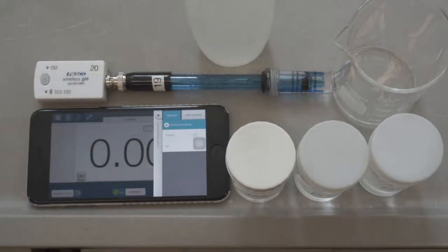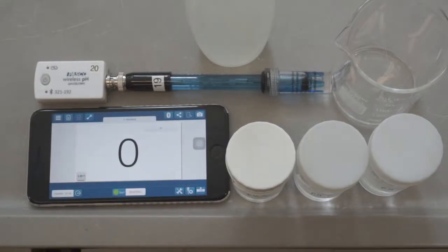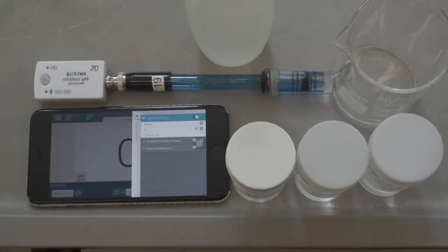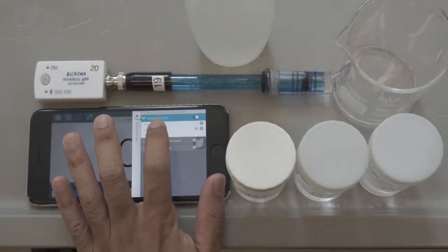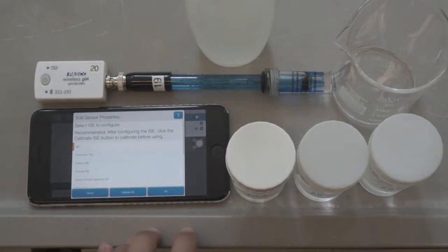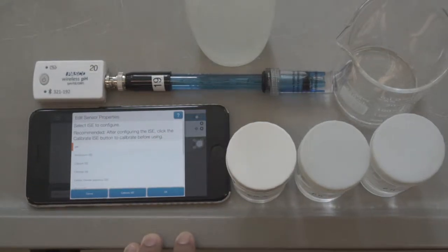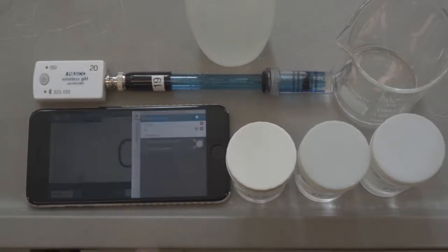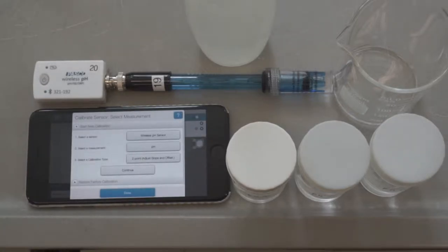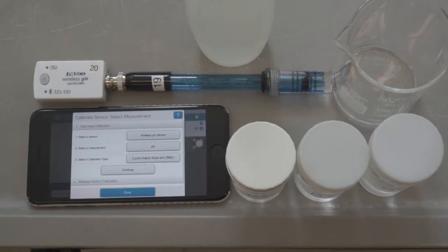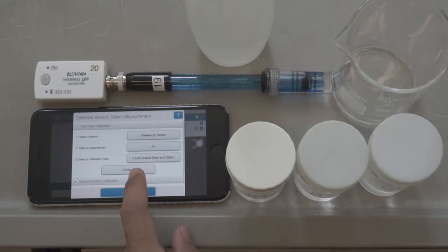Next, click the Select Measurement option. Select the pH option. Click the Calibration icon. It is in the middle of the three icons in the bottom right-hand corner of your screen. Press Calibrate ISE. Pick the pH option and press Calibrate ISE. You are now at the calibration screen. Press Continue.